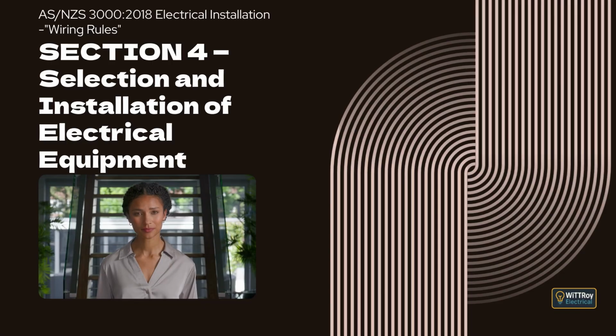Clause 4.1.3, External Influences. This clause explains that all electrical equipment must have characteristics suited to the conditions it is likely to be exposed to so it will function properly at its installed location. It explains that this suitability may come from the equipment's own design and construction or from additional protective measures provided as part of the installation, as long as those measures do not interfere with correct operation.